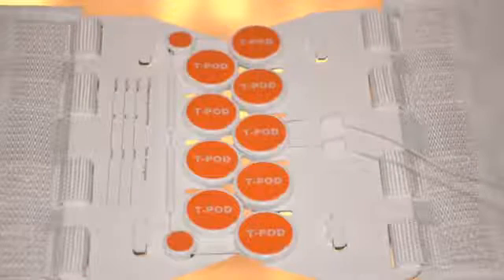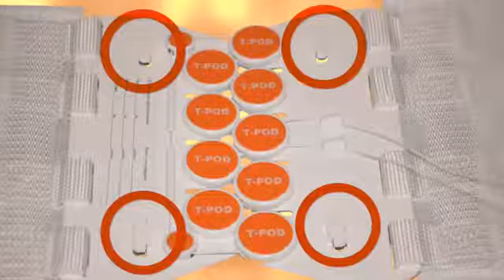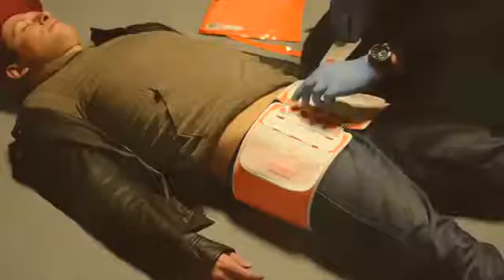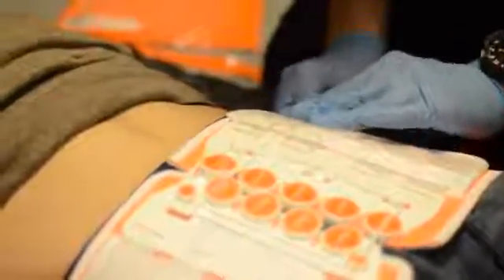The locking hooks, seen here, are four small composite hooks molded into the surface of the adjustment mechanism. These hooks are used to store and secure the 36-inch or 91-centimeter long cord of the adjustment mechanism. Properly used, they prevent accidental loss of circumferential pressure due to rapid and uncontrolled loosening of the adjustment mechanism. They are necessary to shorten the adjustment cord so that the pull tab can be safely secured to the front of the adjustment mechanism.